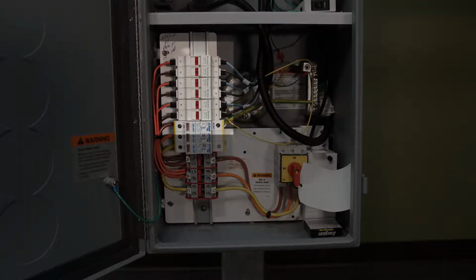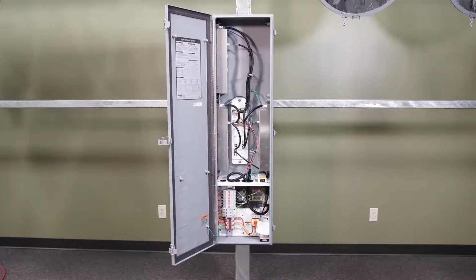Power travels from the disconnect to the distribution blocks, which will either have an A, B, and C block, or it may have just an A and B block in a phase-to-phase configuration. If your site is power phase to neutral, you will also have a neutral block marked N. Power then travels to the line side of the fuse holders, left side.